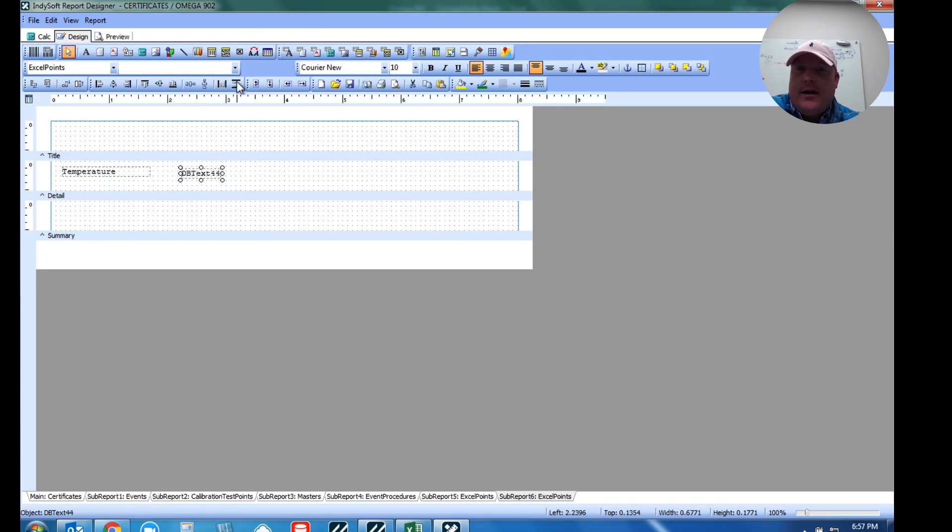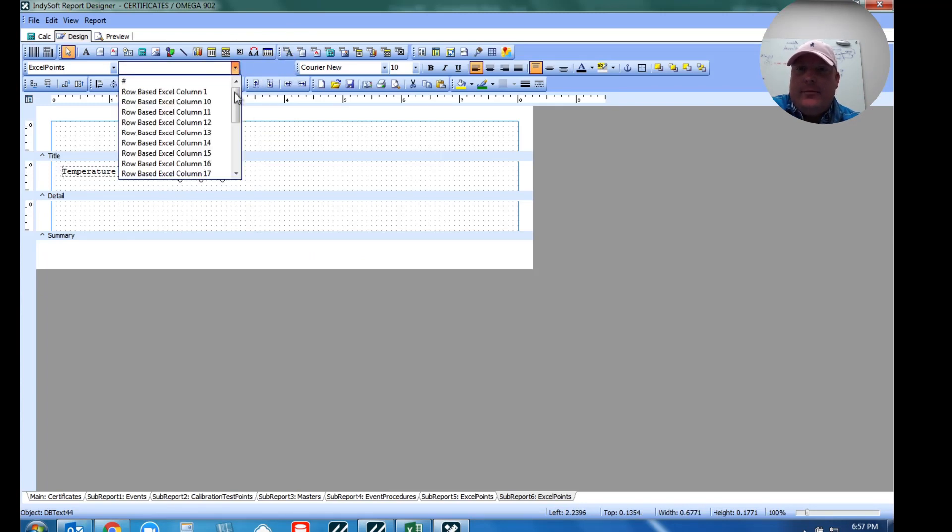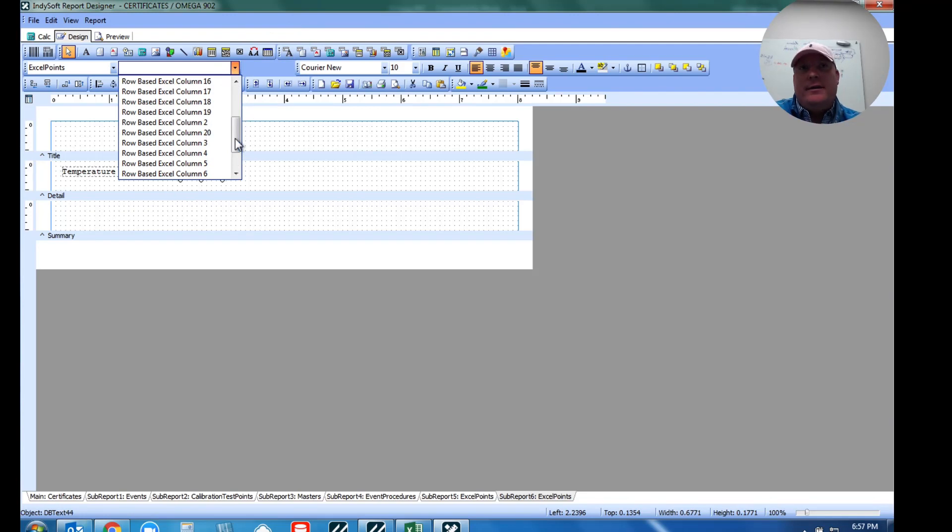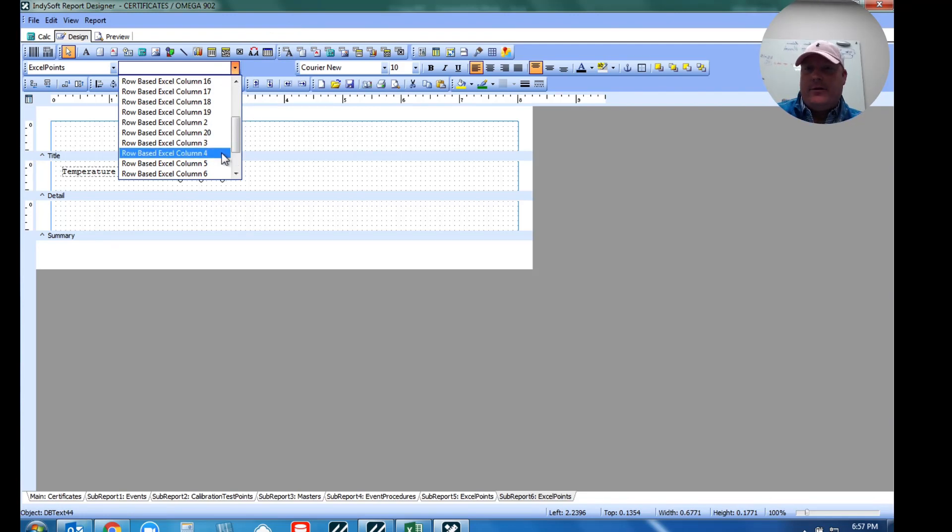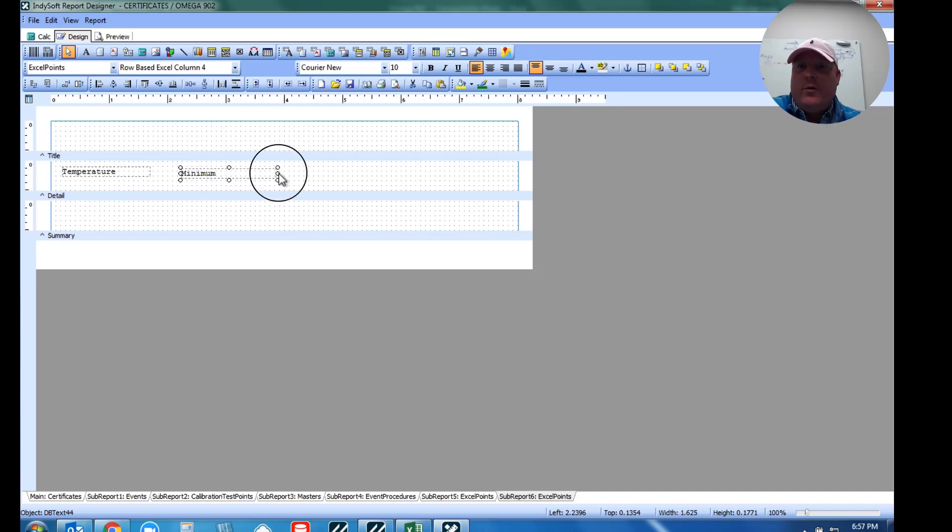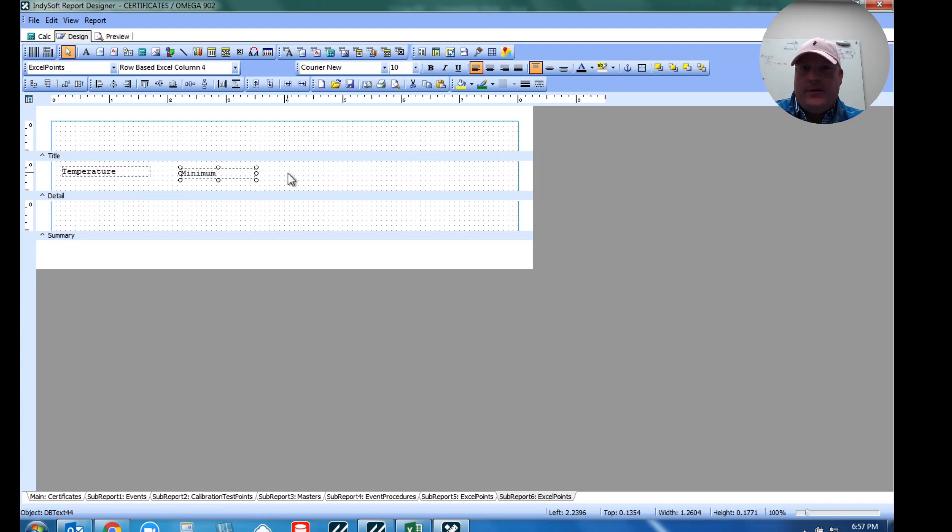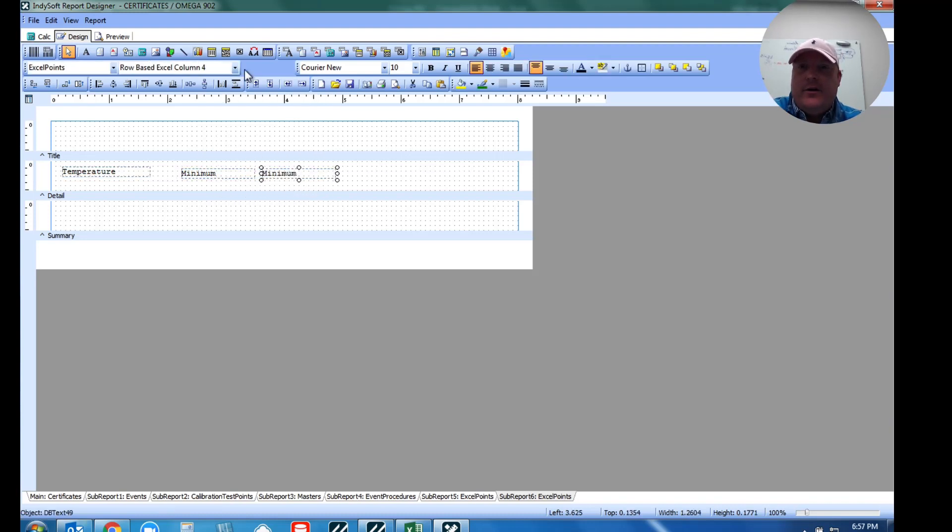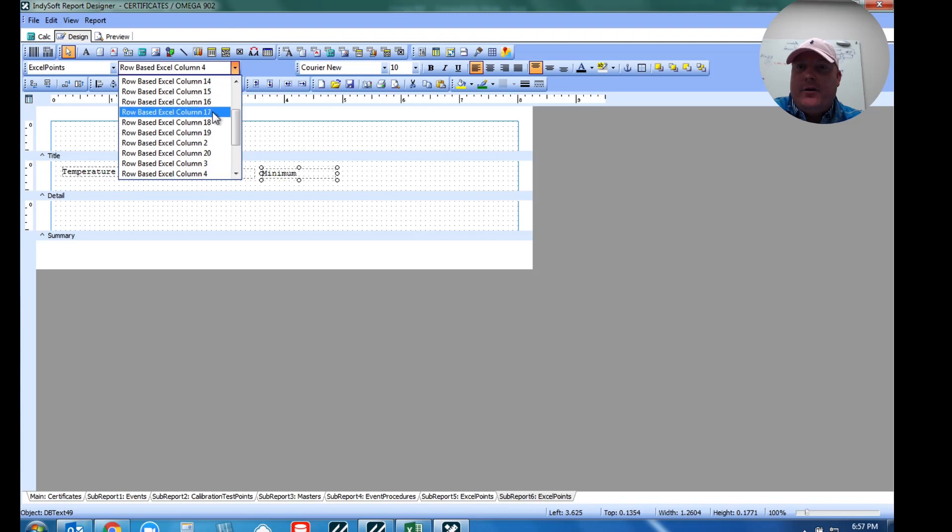So in here what I want to do is simply just choose row one because row one, which was actually column A in Excel, that's where we're storing this column right here. Now right here you'll notice this is row D. So for me I need to grab another database field. But this time I'm going to grab row four, because D, A, B, C, D, one, two, three, four, you kind of get the math on the concept there. So for me my minimum is actually row or column four in Excel. As we get going a little bit faster, you can do things like copy and paste and just move that over. And then I can go to row six because that was where I had my maximum. And then for me I had row eight was my as found and then row nine was my as left.